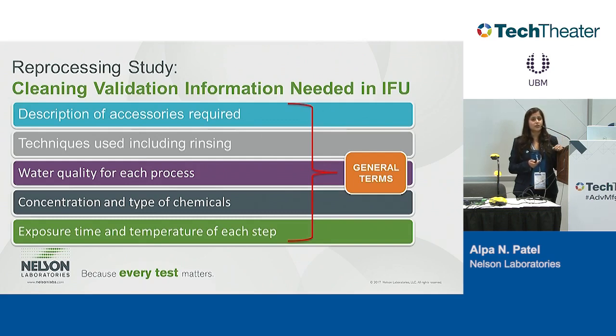Same thing with the dental instrument. The client called us and said, well, we just wipe it with IPA. And they won't do it because it's not a cleaning. IPA is considered disinfection. So you don't have a cleaning process. So you have to validate the cleaning separately from the disinfection. So these are questions I just got this year. So it's not something that happened years ago. This is recent, that we're still seeing.